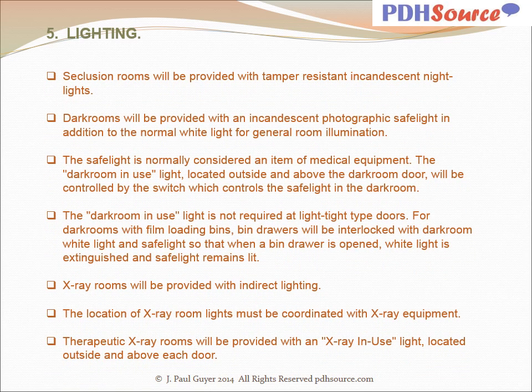Seclusion rooms will be provided with tamper-resistant incandescent nightlights. Dark rooms will be provided with an incandescent photographic safe light in addition to the normal white light for general room illumination. The safe light is normally considered an item of medical equipment. The darkroom in use light located outside and above the darkroom door will be controlled by the switch which controls the safe light in the darkroom. The darkroom in use light is not required at light tight type doors.